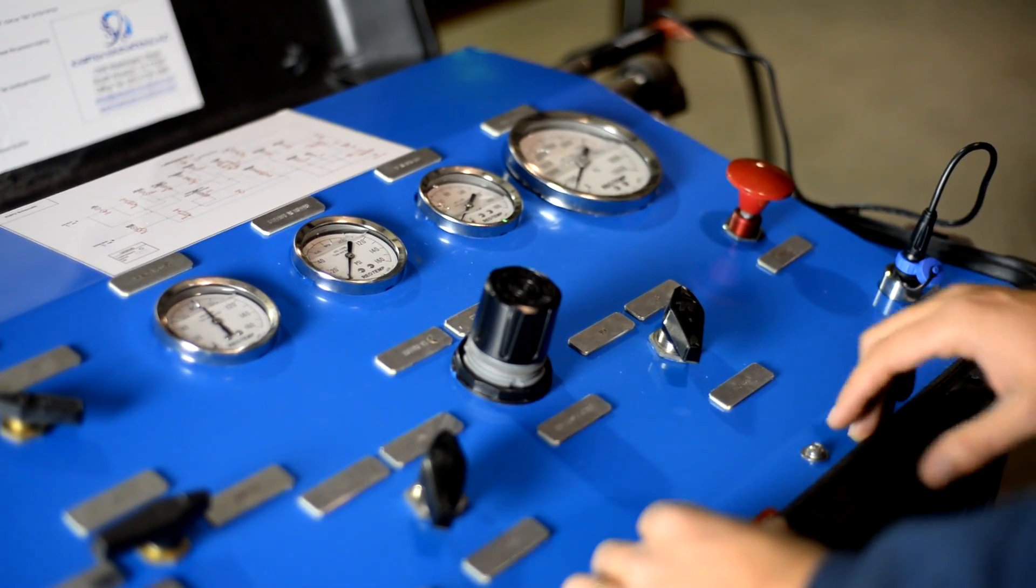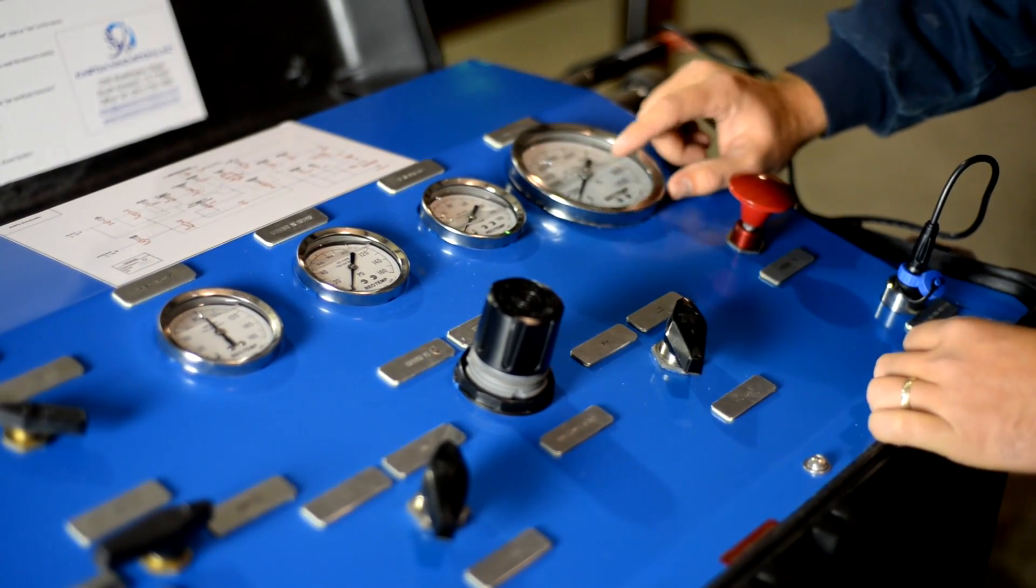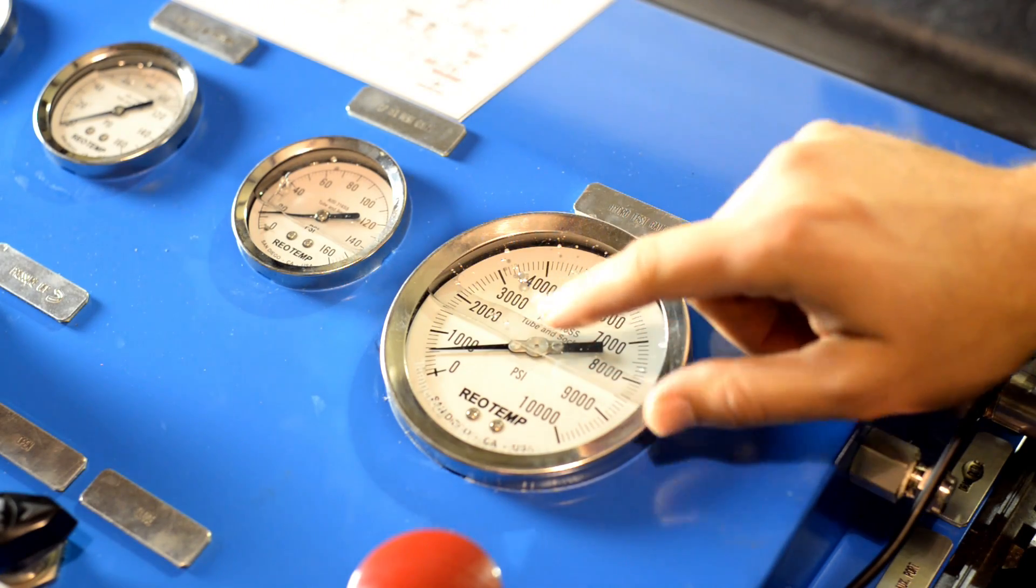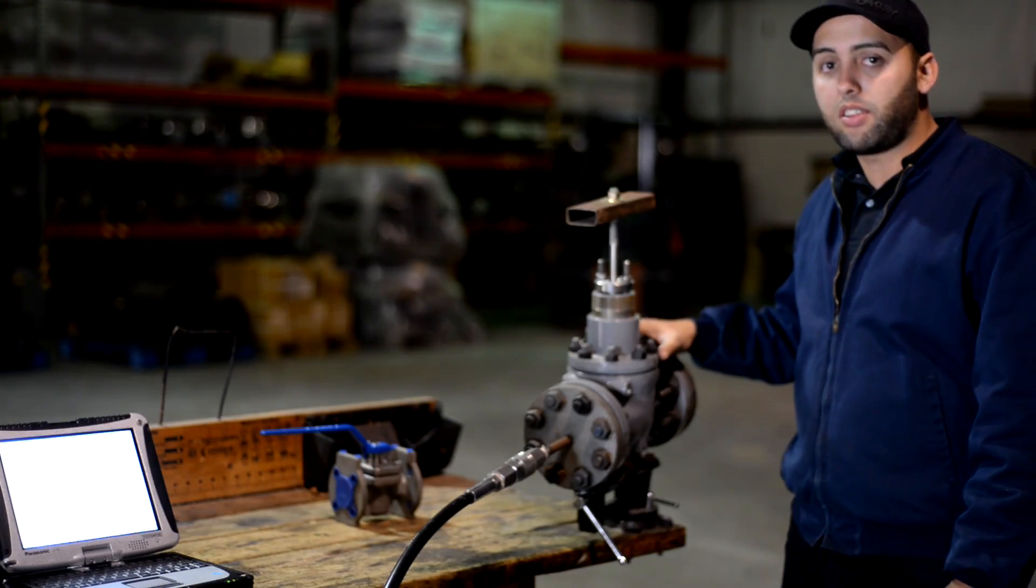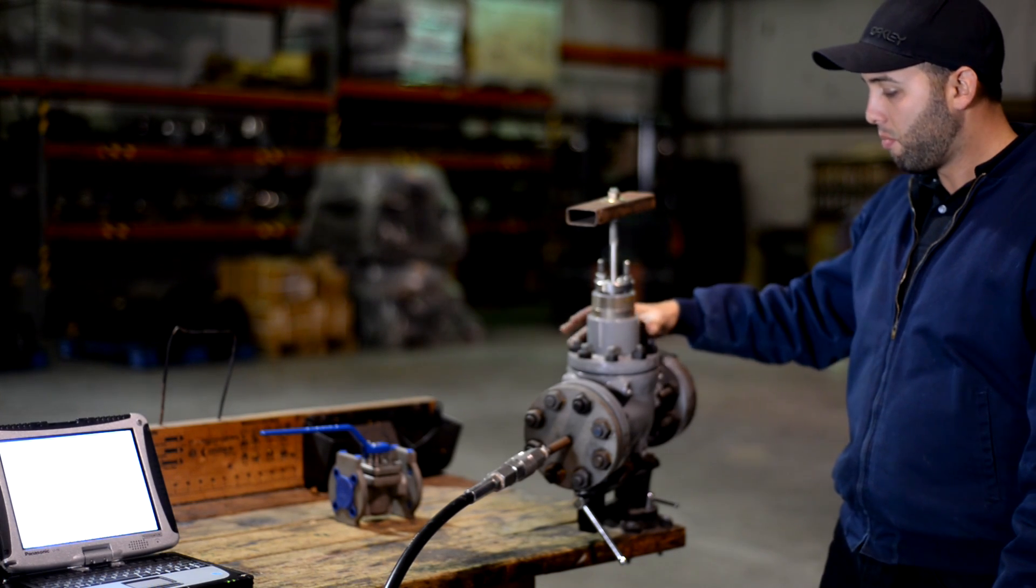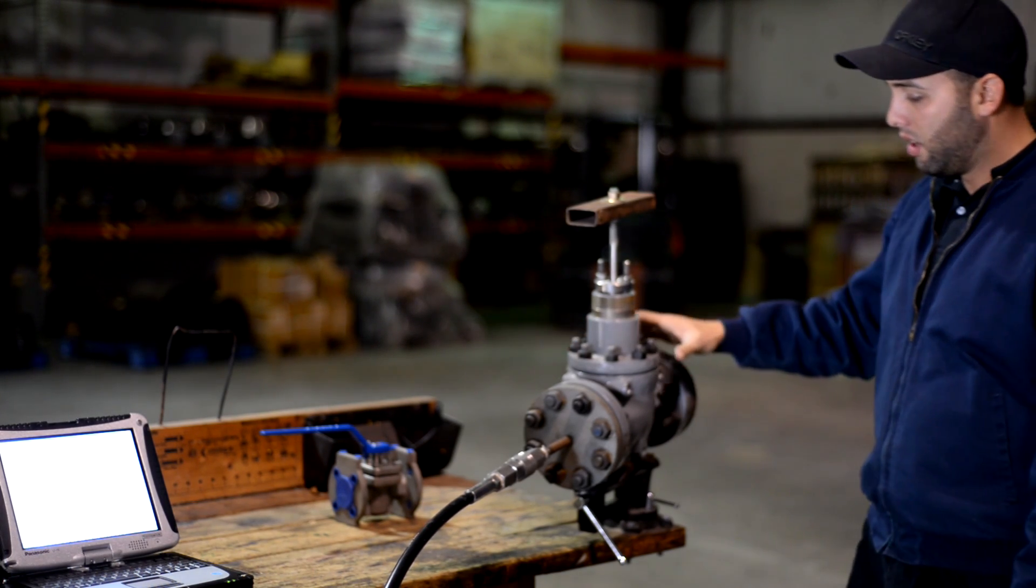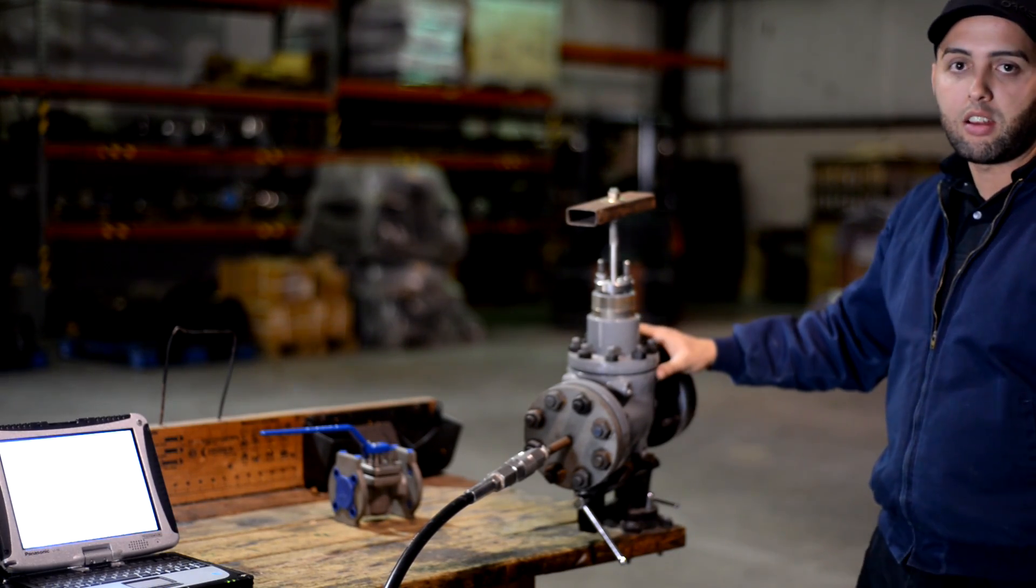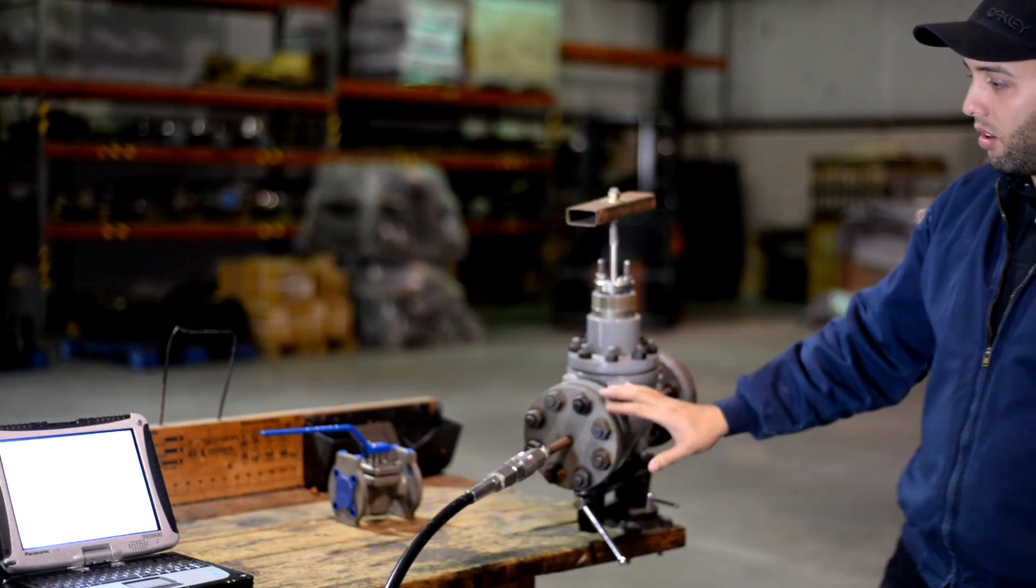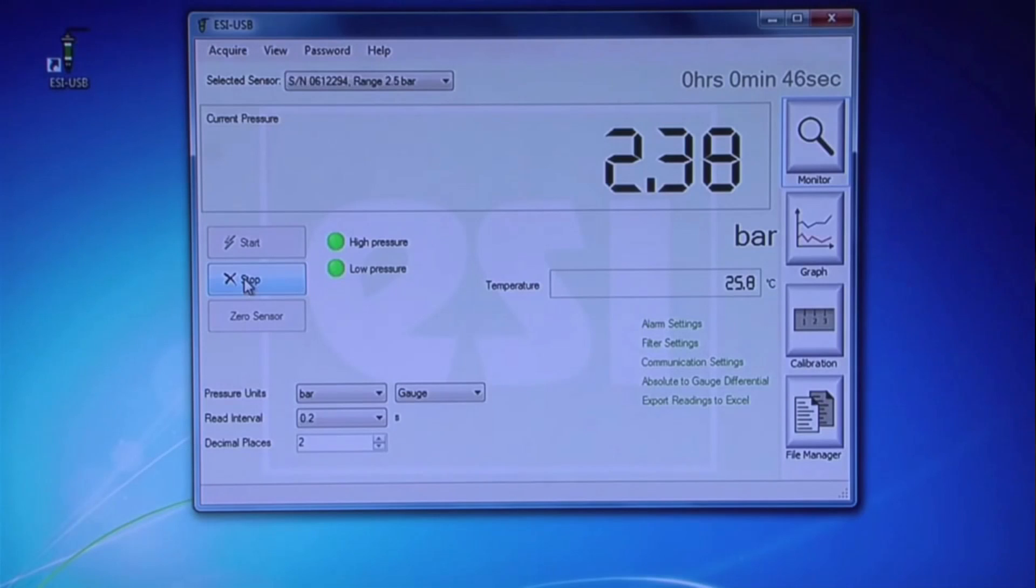While monitoring the hydrostatic test gauge, ensure there's no drop on the reading. Once the desired pressure has been achieved, ensure there's no leakage in your valve according to the standard of your valve testing. You can monitor pressure, temperature, and time on your computer.